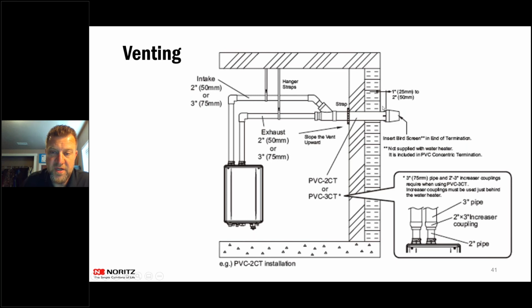So this one, you're pulling combustion air right here next to the house, and it's exhausting straight out. So we always call these the bazookas because they look like bazookas going through the wall. So you can use those concentric terminations. You can use the flat wall terminations that the HVAC guys use for the furnaces. You can also use those types of concentric terminations with our units. But every manufacturer is different on what type of concentric terminations you can use. With ours, it is that bazooka one there, or those flat wall terminations that you can use going out there. Pretty much any concentric PVC termination is approved with our units.